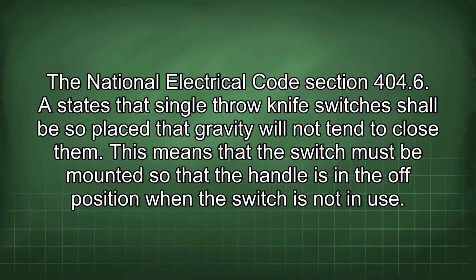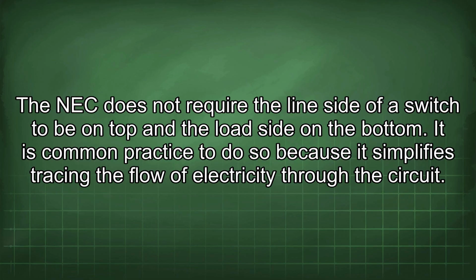The National Electrical Code Section 404.6 states that single-throw knife switches shall be so placed that gravity will not tend to close them. This means that the switch must be mounted so that the handle is in the off position when the switch is not in use. The NEC does not require the line side of a switch to be on top and the load side in the bottom. It is common practice to do so because it simplifies tracing the flow of electricity through the circuit.